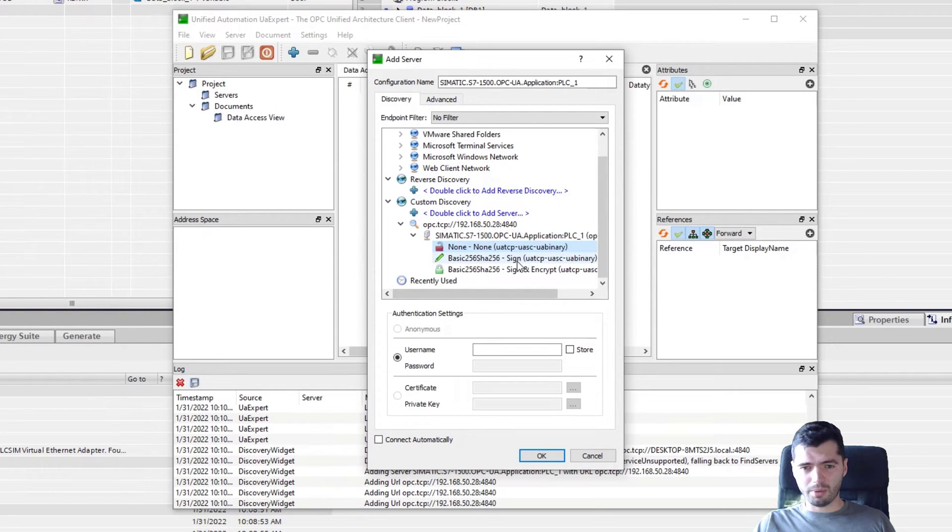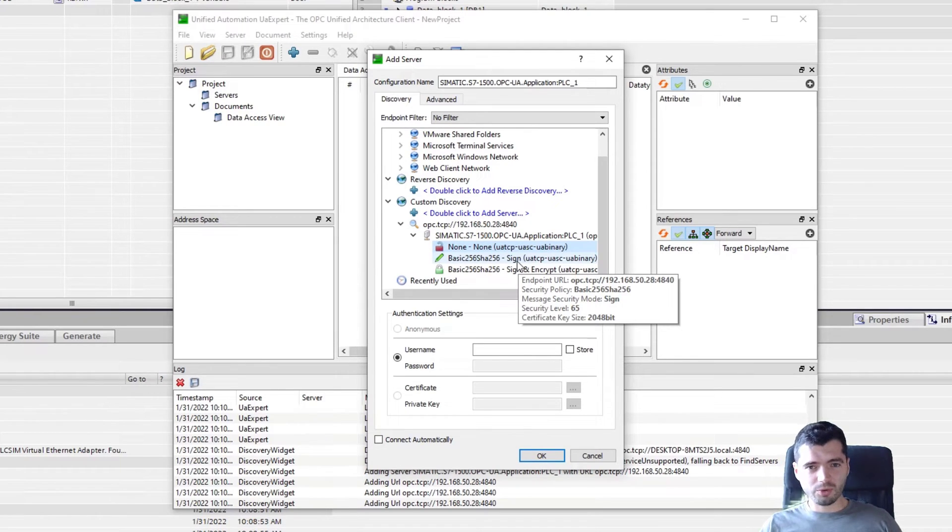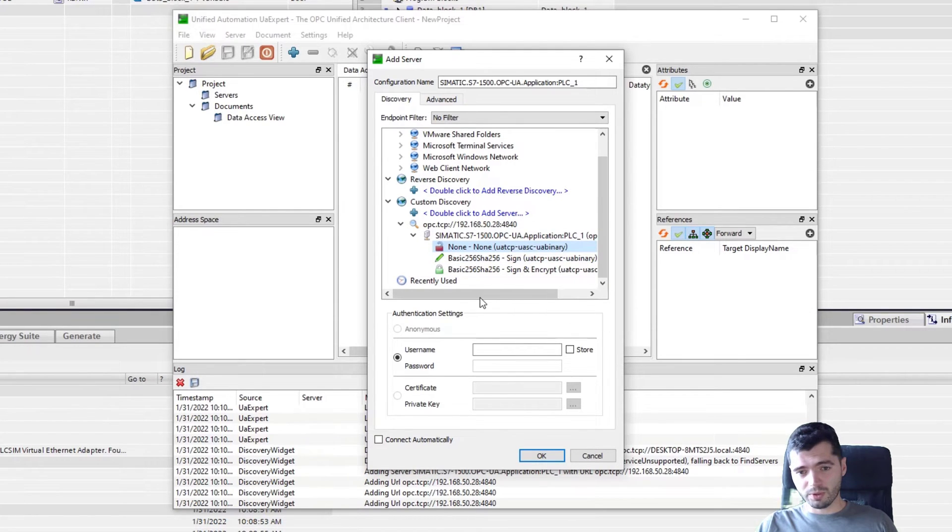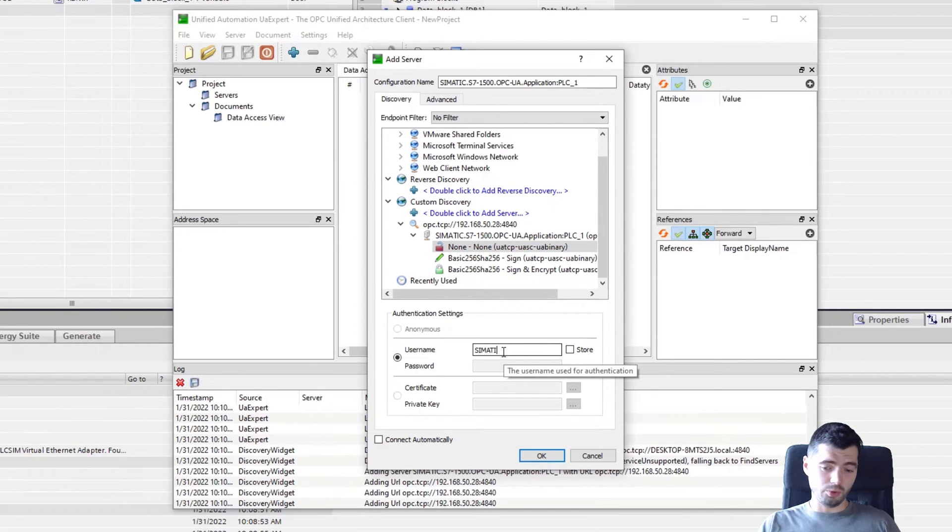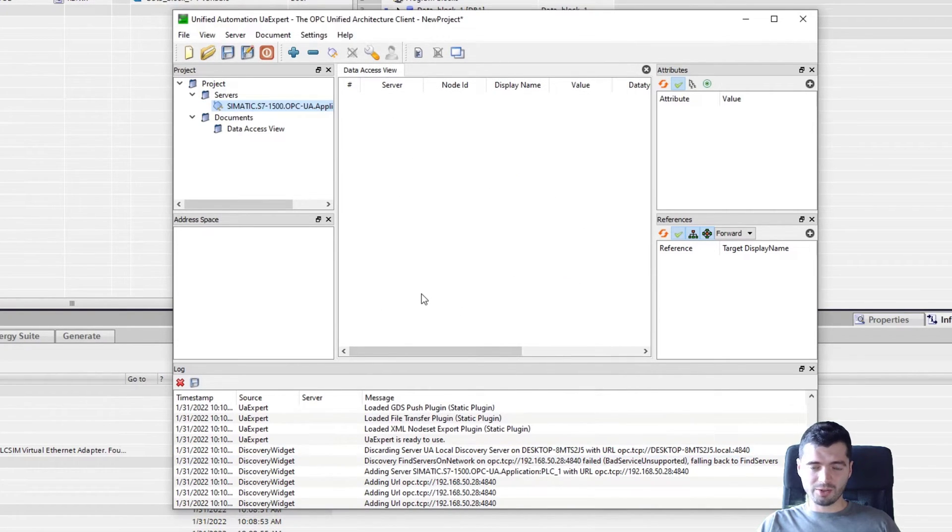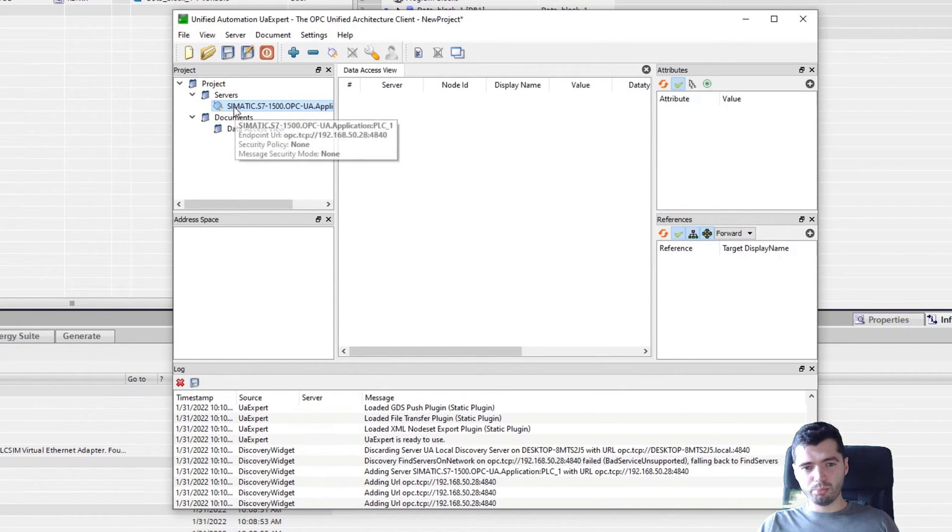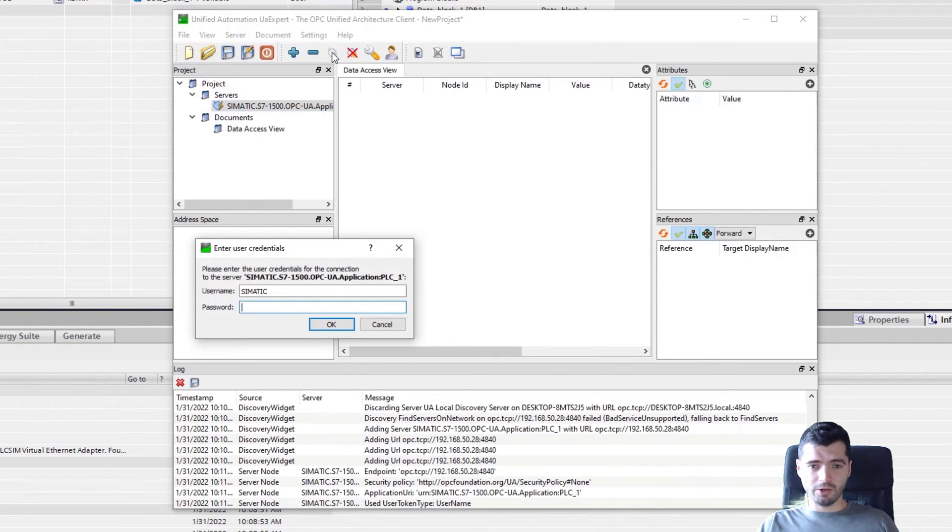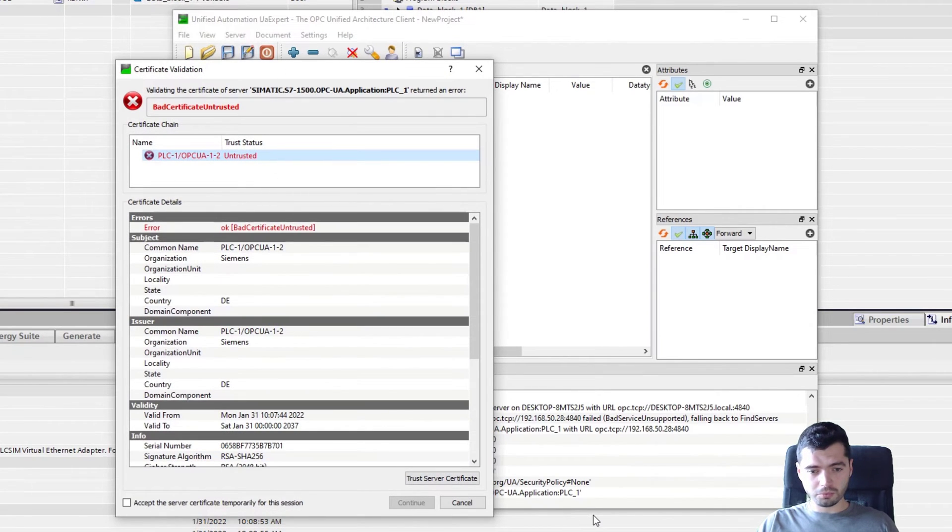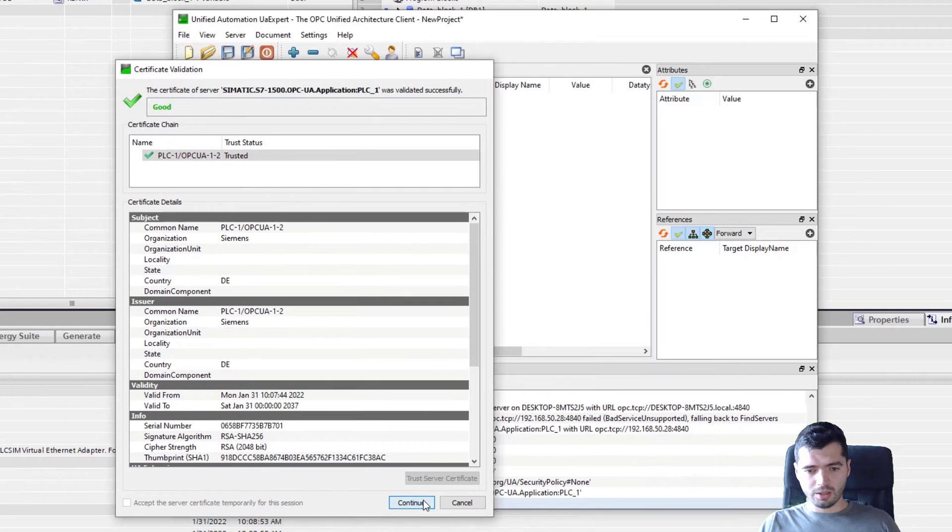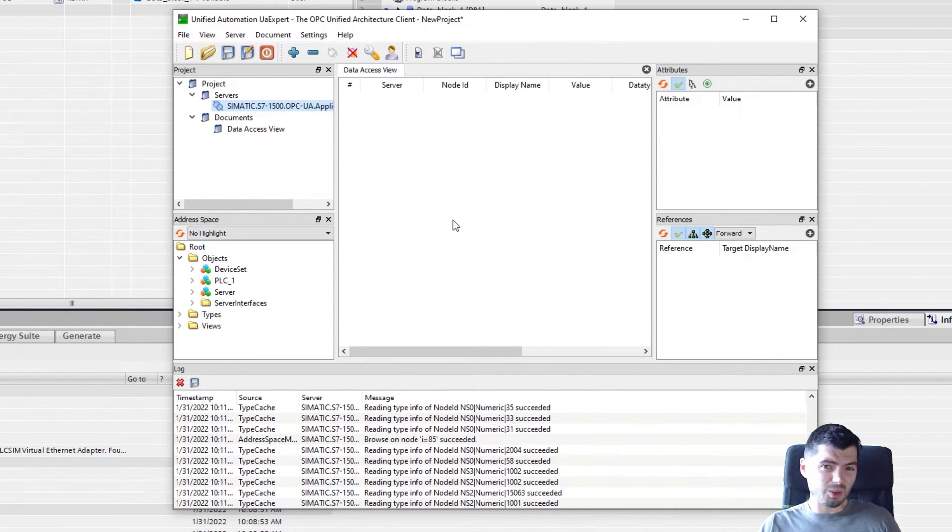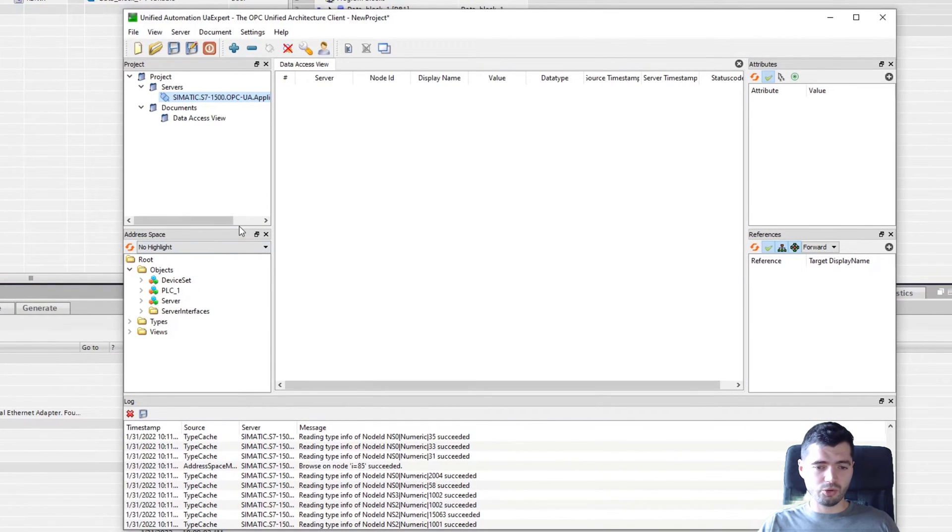So here, as you remember, I left none enabled so that I can log in without certificates because I didn't want to focus on certs. I just wanted to show you very quickly how to set up the OPC UA server and I disabled the guest login, which is why it now asks me for username and password. So I can provide username, I can't provide password at this stage because it will ask me every time I want to connect. So now on the left hand side, under my project, it added this server and if I click connect server, it will ask me for the password that I defined in TIA. Because I didn't load the certificates, it says this certificate is untrusted, do you want to trust it or not? I want to trust it, I'm happy with this, but normally I would advise you to use certificates and encrypted communication.